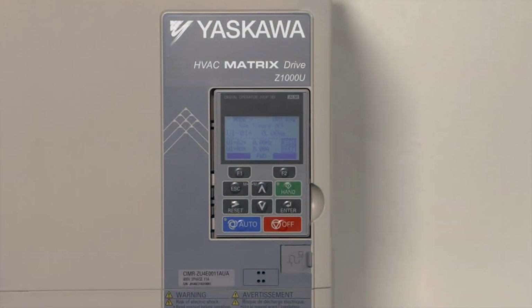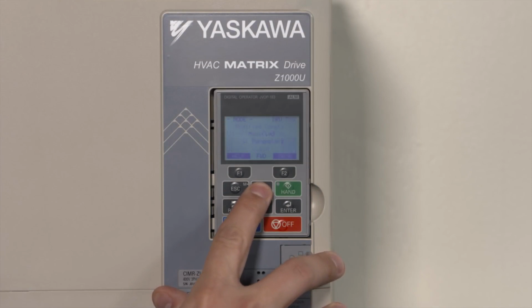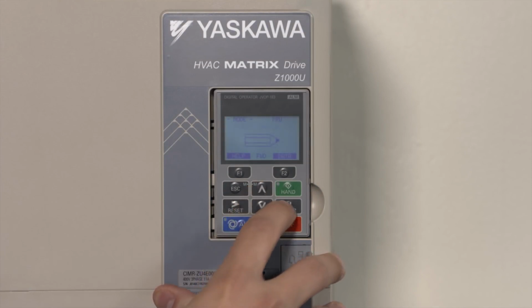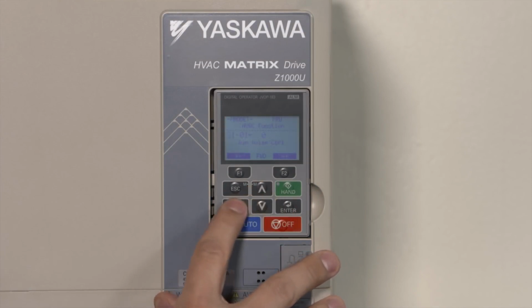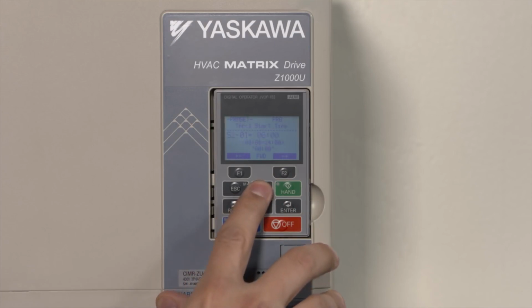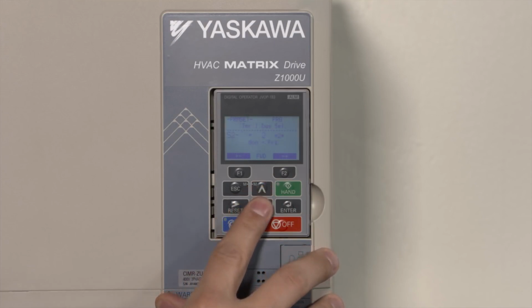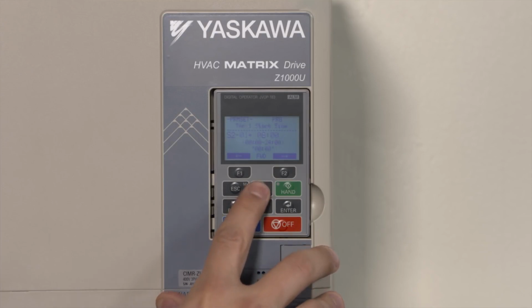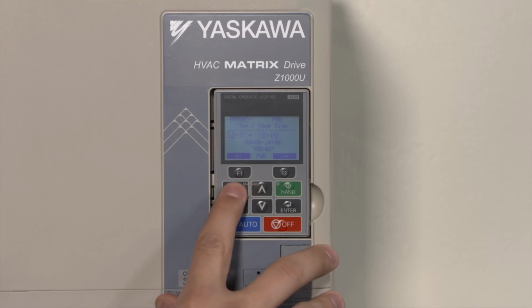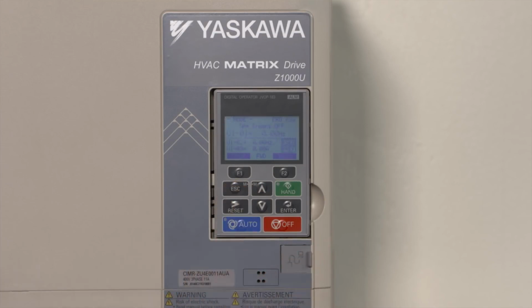The Z1000U has a keypad with a programmable real-time clock. This clock can be used to set start and stop sequencing timers. For example, the Z1000U can be programmed to run Monday through Friday from 6 a.m. to 6 p.m. while a building is occupied. With the real-time clock, fault log events can be stamped with date and time, making troubleshooting easier.